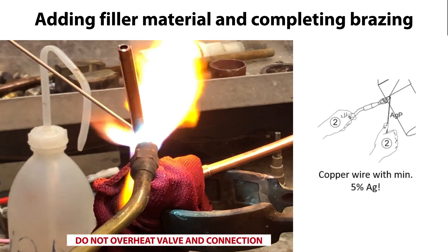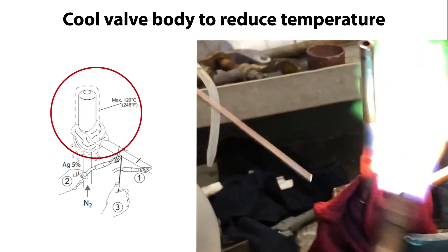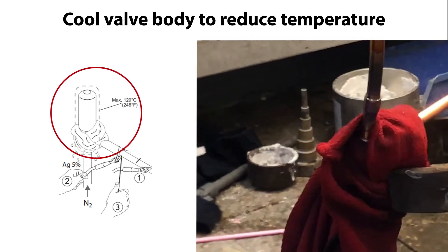For such a small valve the complete procedure only takes a few seconds, so take care not to overheat the valve and connections. Ensure that the max allowable valve body temperature is not exceeded during brazing as specified here. This is done by ensuring that the cloth around the valve remains wet, here seen with water boiling from the cloth.